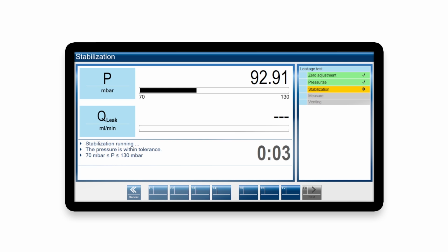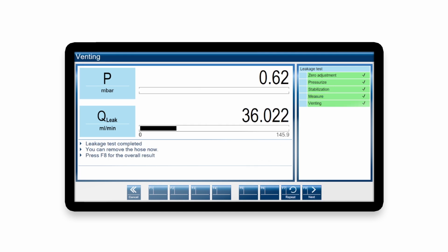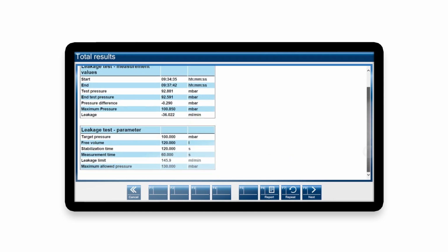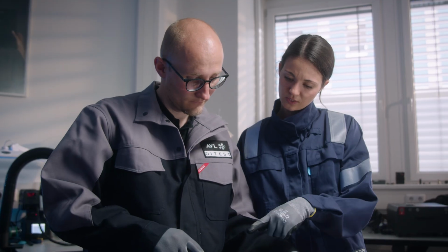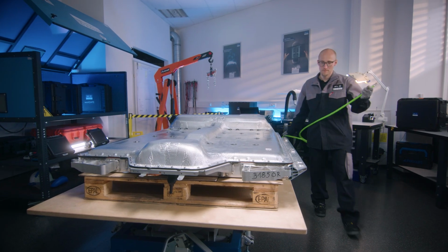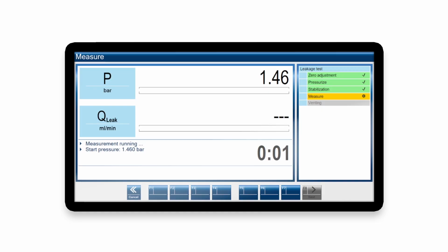It's very common that an untight battery housing contains too high humidity, or an untight cooling system could flood the battery. If you suspect the battery is filled with water, you have to avoid unnecessary repositioning and tipping of the battery. As a next step, you can perform the leak test of the cooling system.